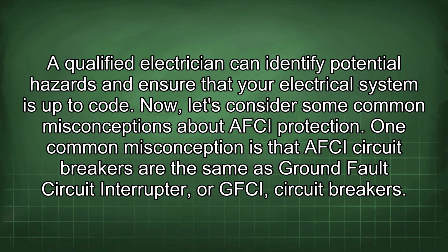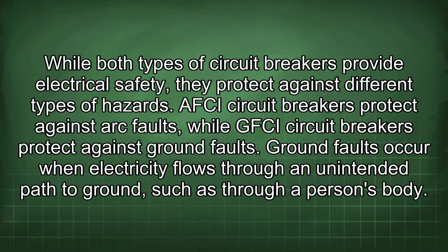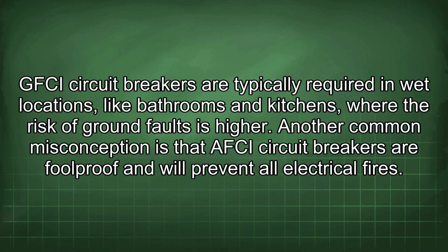Now, let's consider some common misconceptions about AFCI protection. One common misconception is that AFCI circuit breakers are the same as ground fault circuit interrupter, or GFCI, circuit breakers. While both types of circuit breakers provide electrical safety, they protect against different types of hazards. AFCI circuit breakers protect against arc faults, while GFCI circuit breakers protect against ground faults. Ground faults occur when electricity flows through an unintended path to ground, such as through a person's body. GFCI circuit breakers are typically required in wet locations like bathrooms and kitchens, where the risk of ground faults is higher.